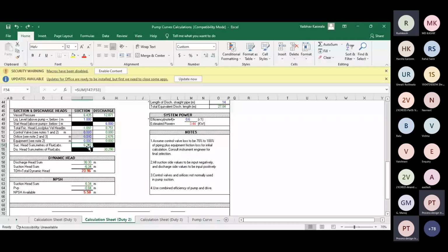ओके. वही चीज मैंने पहले पूछा था ना कि अगर सक्शन प्रेशर हम बढ़ा देते हैं तो हेड बढ़ जाएगा हमारा, तो आपने बोला था पहले. Don't confuse between the head of the pump and pressure of the system. हेड मतलब क्या है, 24 मीटर हेड ही रहा है, पंप का हेड चेंज नहीं हो रहा है, आपका प्रेशर बढ़ा है. मैंने क्या बोला था, सी आप पंप का सक्शन प्रेशर 10 कर दो तो डिस्चार्ज प्रेशर will be 34. तो discharge pressure is 34. हेड तो अभी भी 24 ही है, हेड नहीं बढ़ा है, आपका प्रेशर बढ़ा है. यस. ओके. पहले भी मैंने यही बताया था.